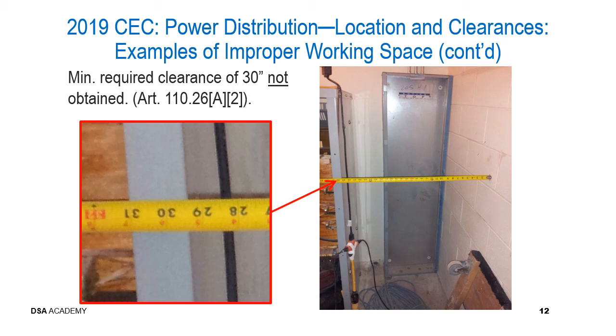Now what we're depicting on the left-hand side is a blow-up view of the tape measure showing that the actual working space width is only around 29.5 or 29 3/8 inches. Now it's unfortunate because you would say, well, it's pretty close, right? Nope, close is not close ever when you're talking about minimum required working spaces in front of dangerous energized equipment. So obviously this is non-compliant.